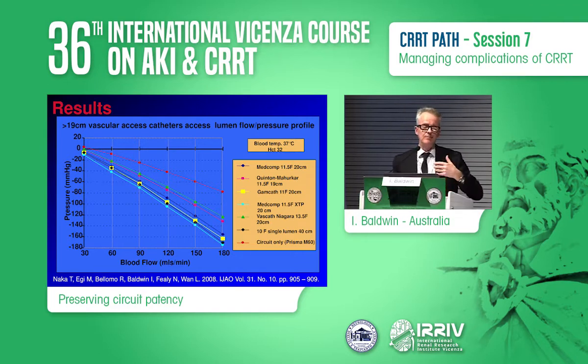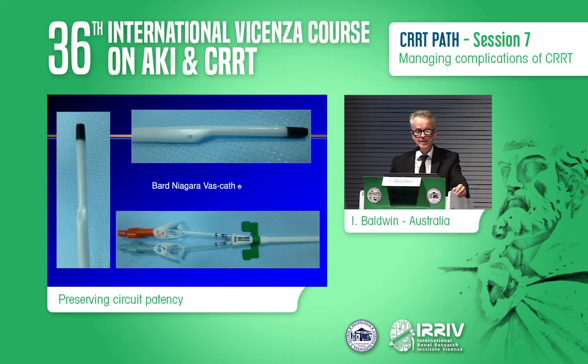And negative pressure, I believe, beyond about minus 50 millimetres of mercury, when it gets to more than minus 100, in itself starts to cause what's called silent or covert flow reduction, and it's something that you can be unaware of. So I'll just briefly mention that.